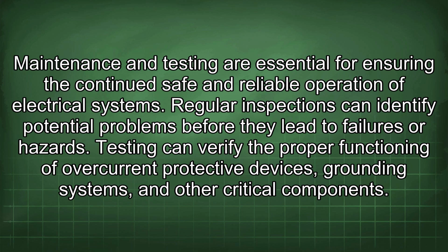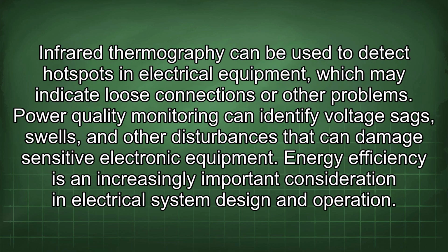Regular inspections can identify potential problems before they lead to failures or hazards. Testing can verify the proper functioning of overcurrent protective devices, grounding systems, and other critical components. Infrared thermography can be used to detect hotspots in electrical equipment, which may indicate loose connections or other problems. Power quality monitoring can identify voltage sags, swells, and other disturbances that can damage sensitive electronic equipment.